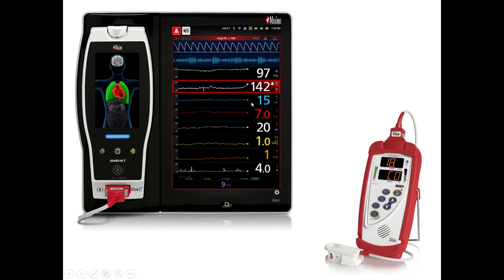In this image, we see two pulse oximeters made by Masimo — a pulse co-oximeter, which uses eight wavelengths, and a pulse oximeter which only uses two wavelengths: one for red and one for infrared.